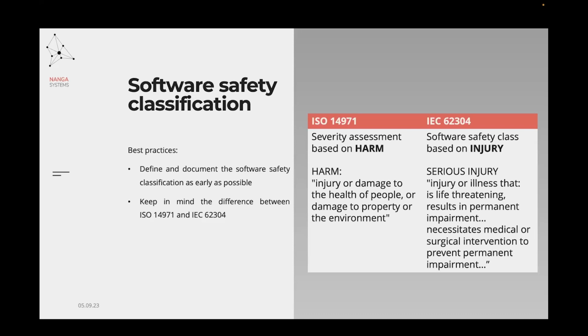Following the guidance of IEC 62304, it is important to keep in mind the difference between ISO 14971 and IEC 62304, as following the guidance of ISO 14971 might lead to a higher classification due to the difference between harm and injury. As you can see on the right-hand side, ISO 14971 uses harm as a base for severity assessment. Harm in this context means injury or damage to health of people or damage to property or the environment. In case of IEC 62304, we are talking about injury, where serious injury means injury or illness that is life-threatening, results in permanent impairment, or necessitates medical or surgical intervention to prevent permanent impairment.